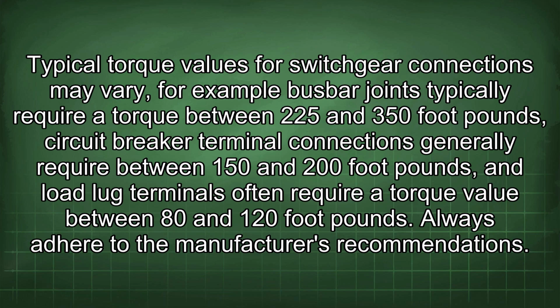For example, busbar joints typically require a torque between 225 and 350 foot-pounds. Circuit breaker terminal connections generally require between 150 and 200 foot-pounds, and load lug terminals often require a torque value between 80 and 120 foot-pounds. Always adhere to the manufacturer's recommendations.